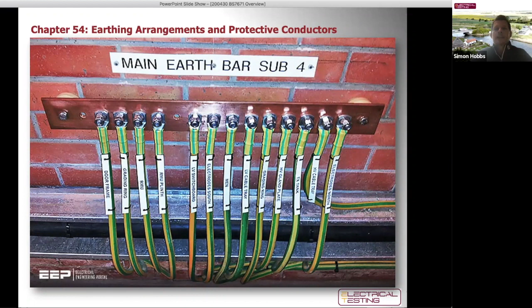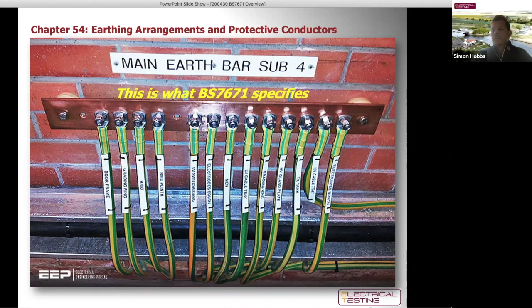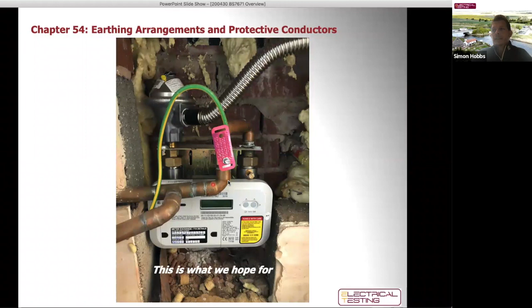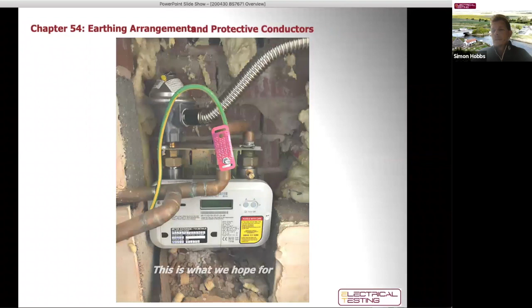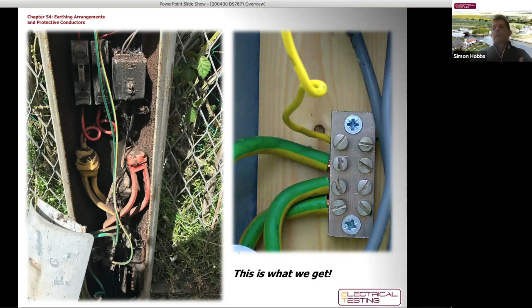BS 7671 specifies that this is what we would like the earthing and the protective conductors to look like. So this is what the regulations are expecting you to install. In reality, this is what we hope to get. We hope that we get the right size earthing conductor. We hope it's connected to the right pipe, and we hope that it's got the right labeling on it. Unfortunately, a lot of the time, this is what we get. Incorrect colored cables, not sure if it is an earthing conductor or a protective conductor. It might be a phase conductor connected to the earth. Not entirely sure how that earth is connected and so on. So we need to be really mindful of what the regulations are requiring compared to what we actually end up getting on site.